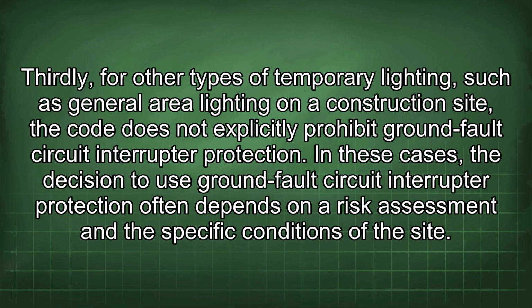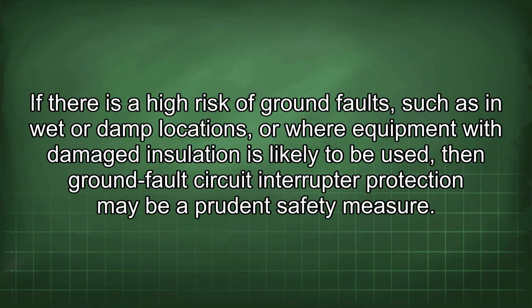Thirdly, for other types of temporary lighting, such as general area lighting on a construction site, the code does not explicitly prohibit ground fault circuit interrupter protection. In these cases, the decision to use ground fault circuit interrupter protection often depends on a risk assessment and the specific conditions of the site. If there is a high risk of ground faults, such as in wet or damp locations, or where equipment with damaged insulation is likely to be used, then ground fault circuit interrupter protection may be a prudent safety measure.